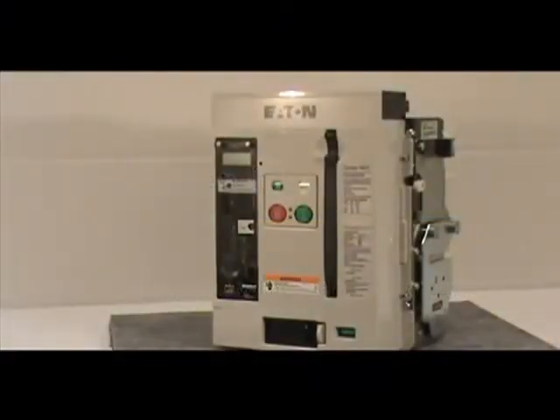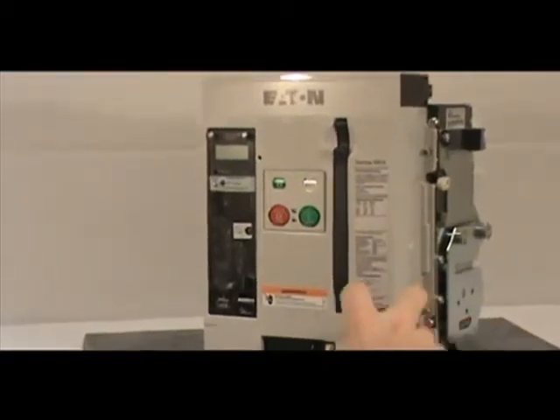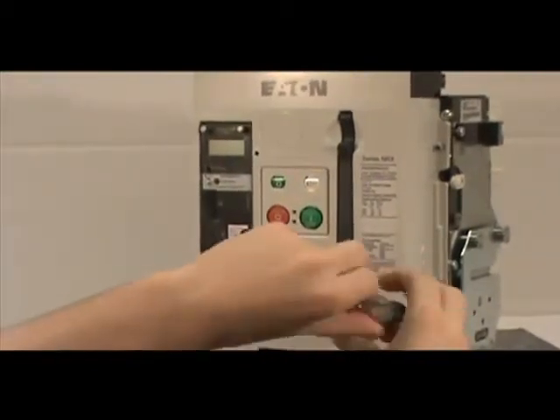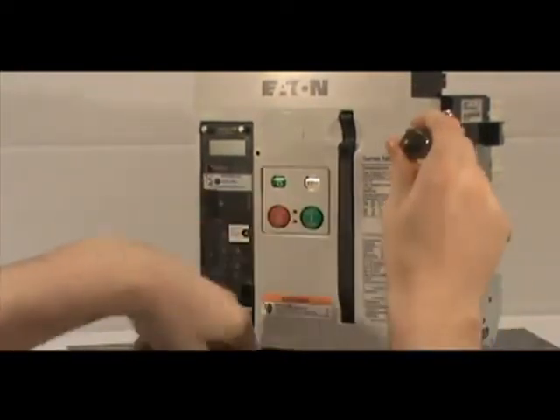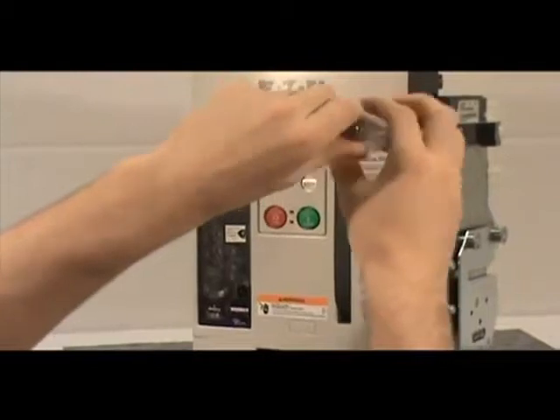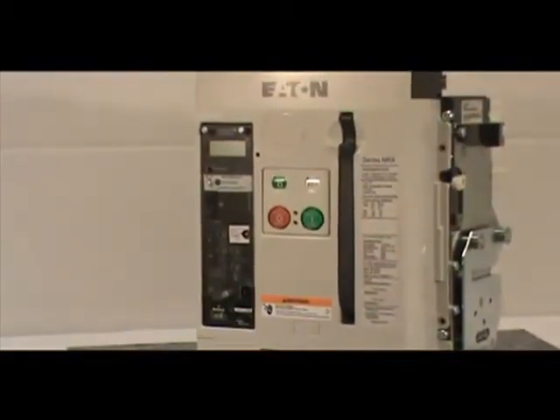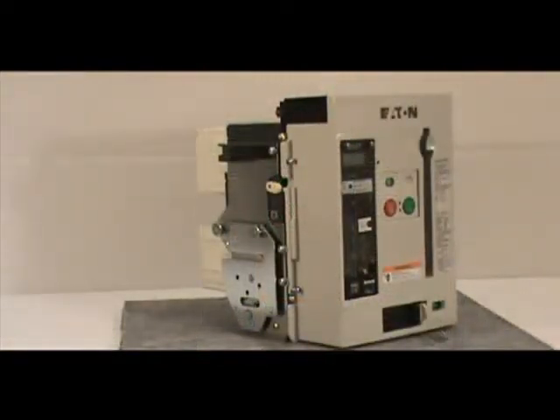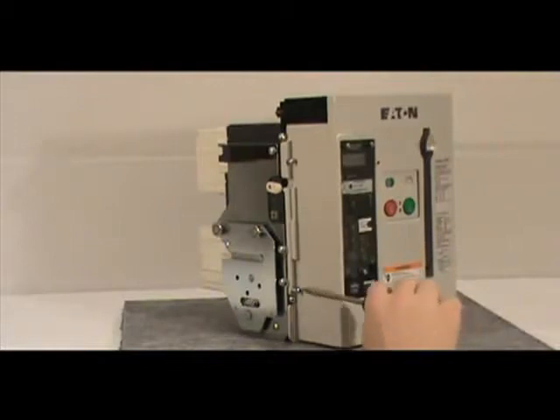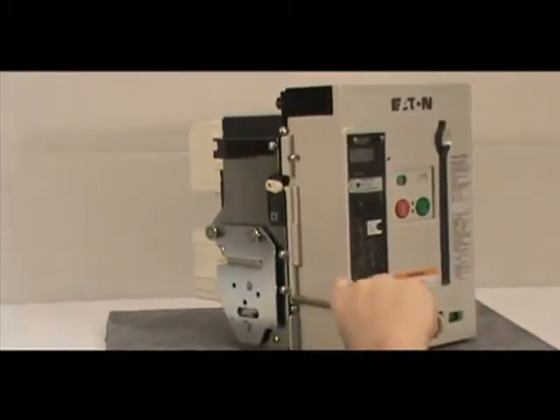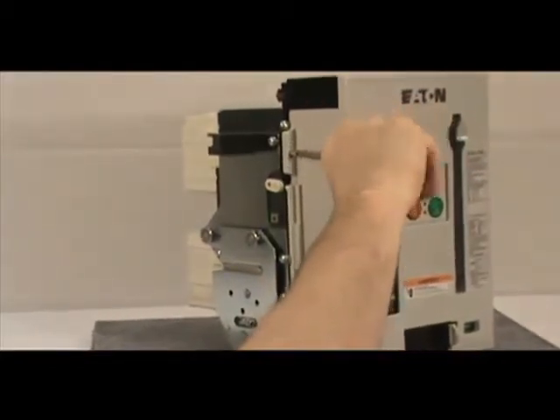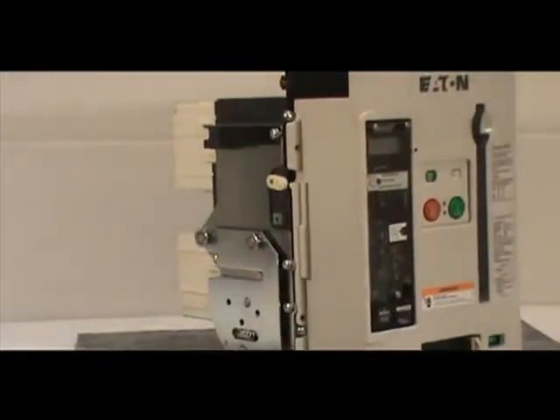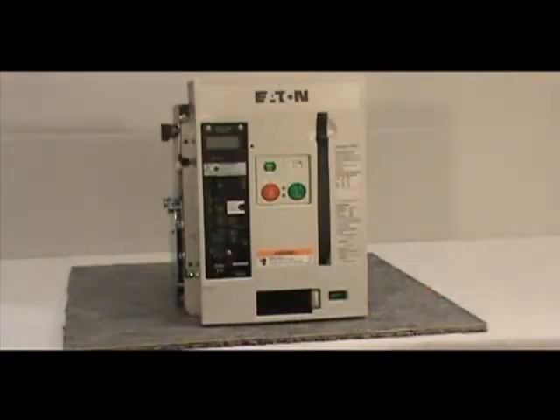Before proceeding with the installation, you must remove the front cover of the circuit breaker. To do this, you must remove the 4 non-captive screws with the number 2 Phillips head screwdriver. If you have a 4-pole breaker, there are 6 screws to be removed. Once you've done this, pull down on the charging handle for easy removal of the cover from the breaker.